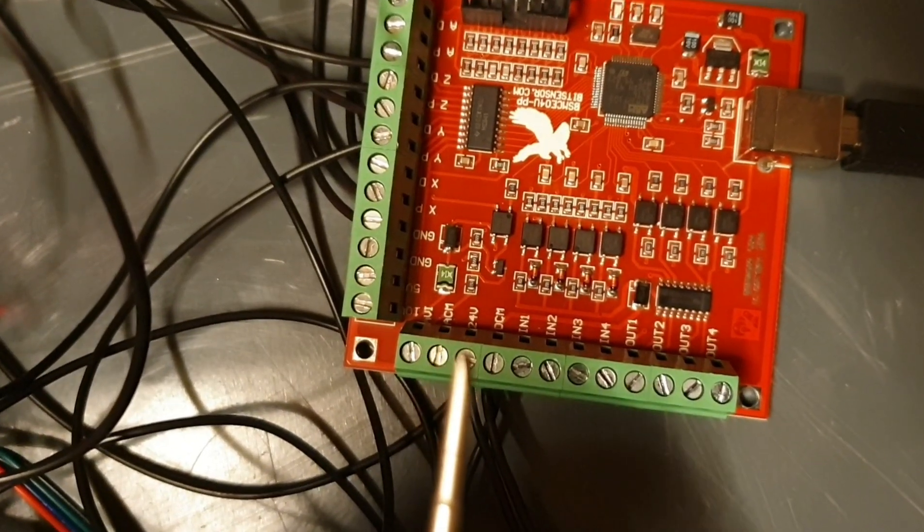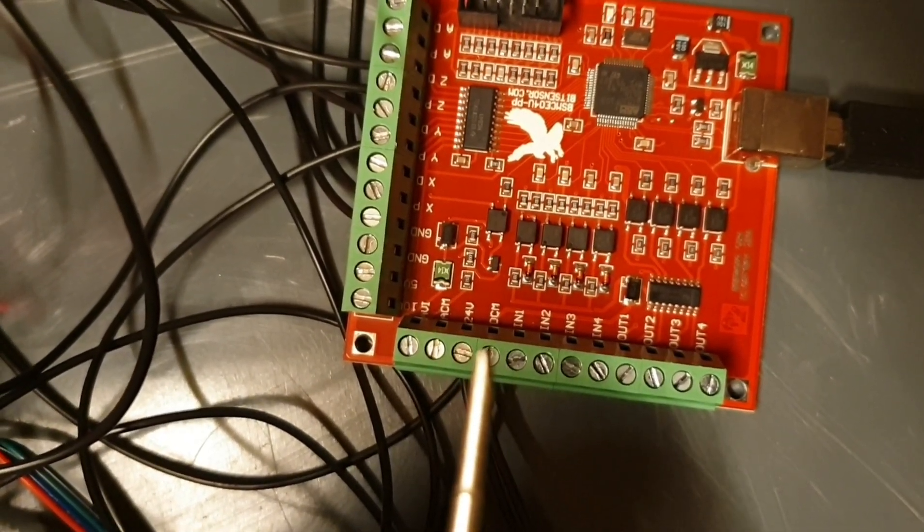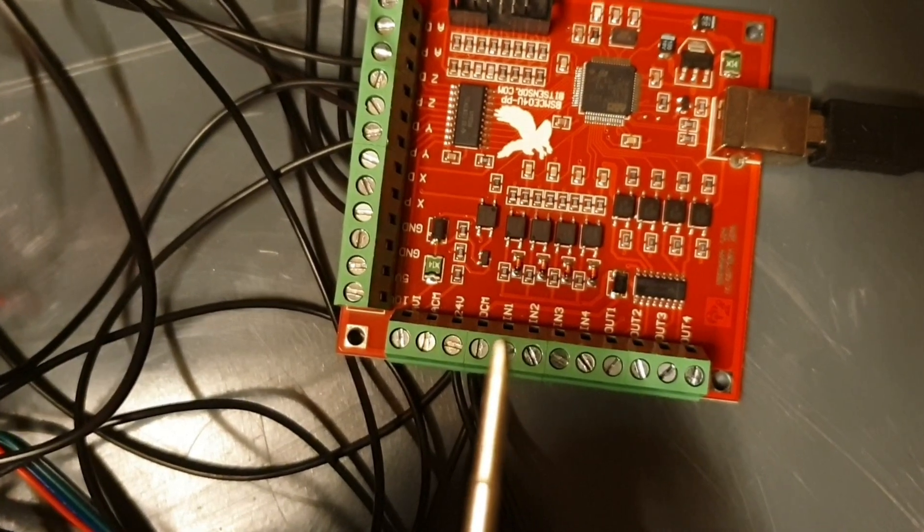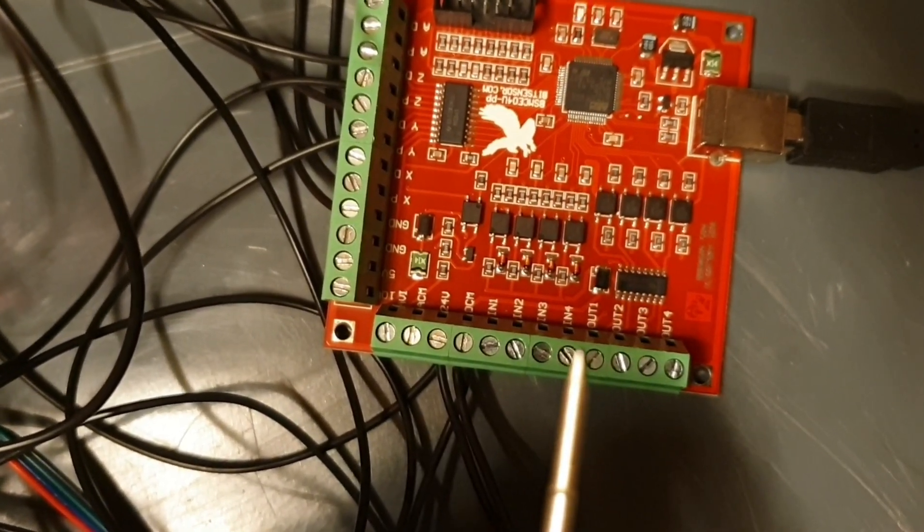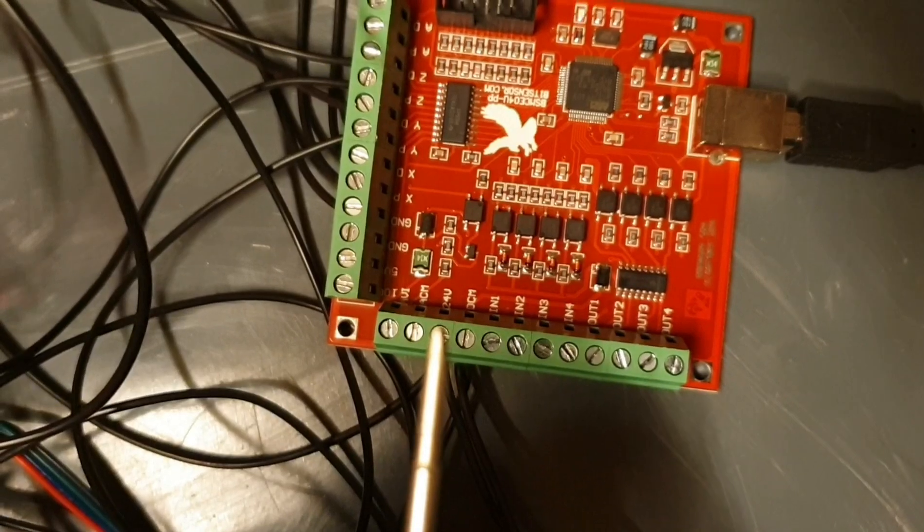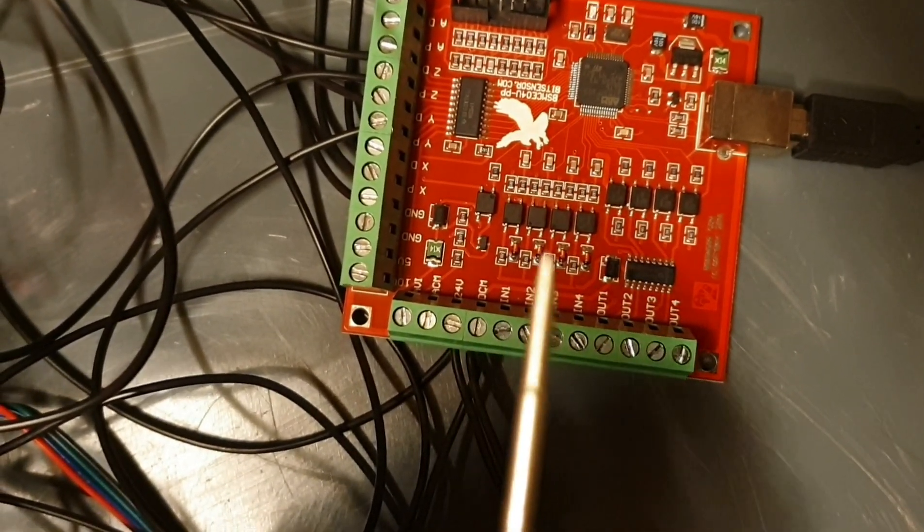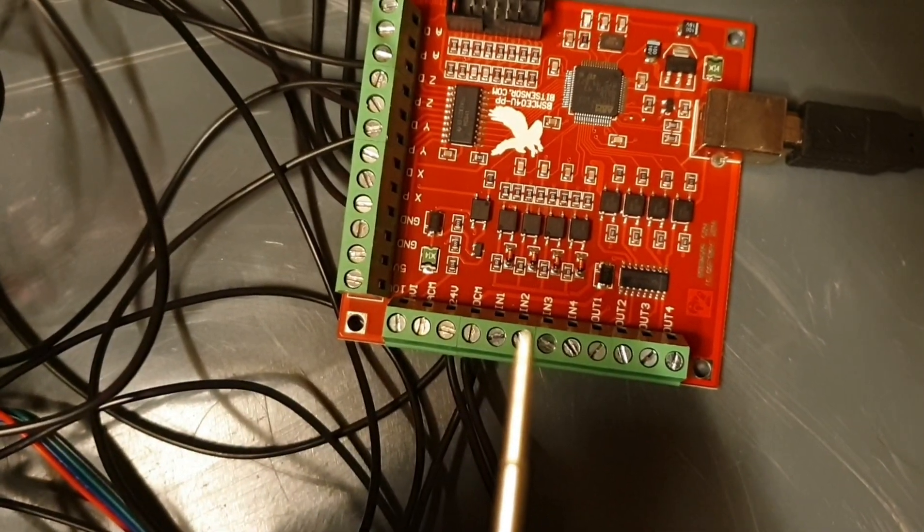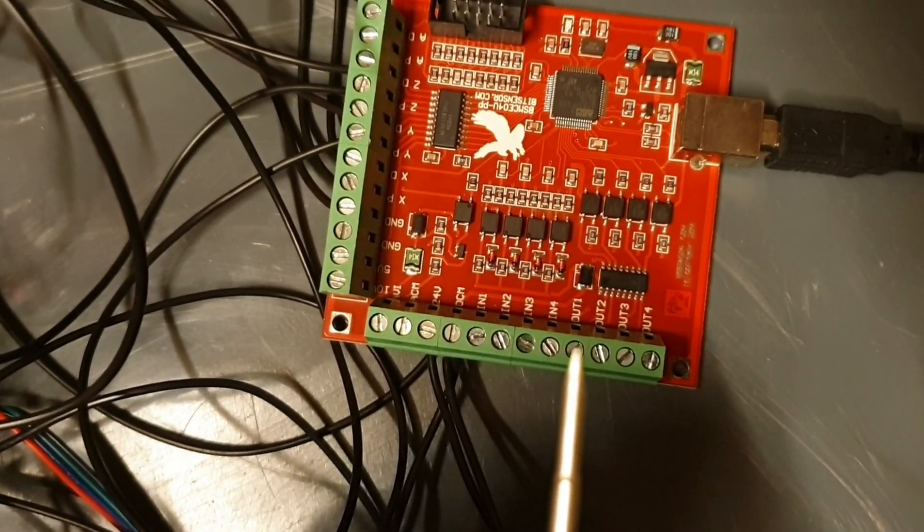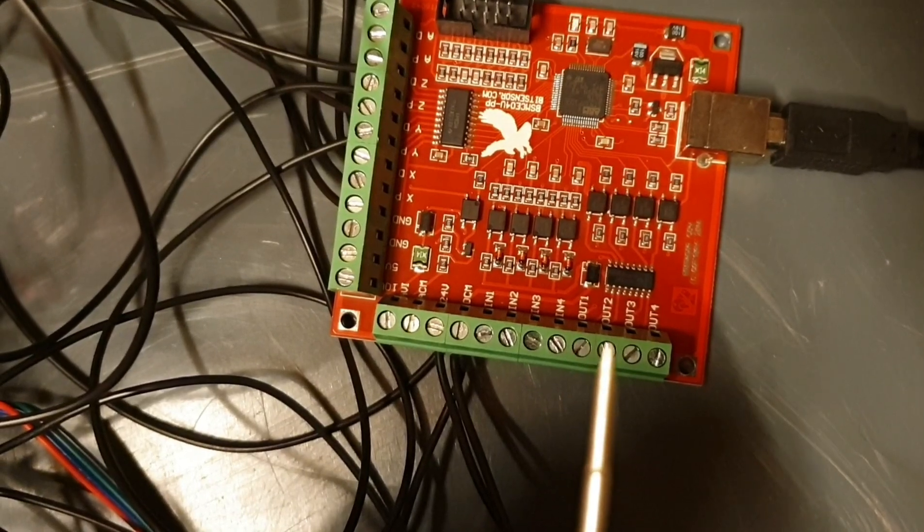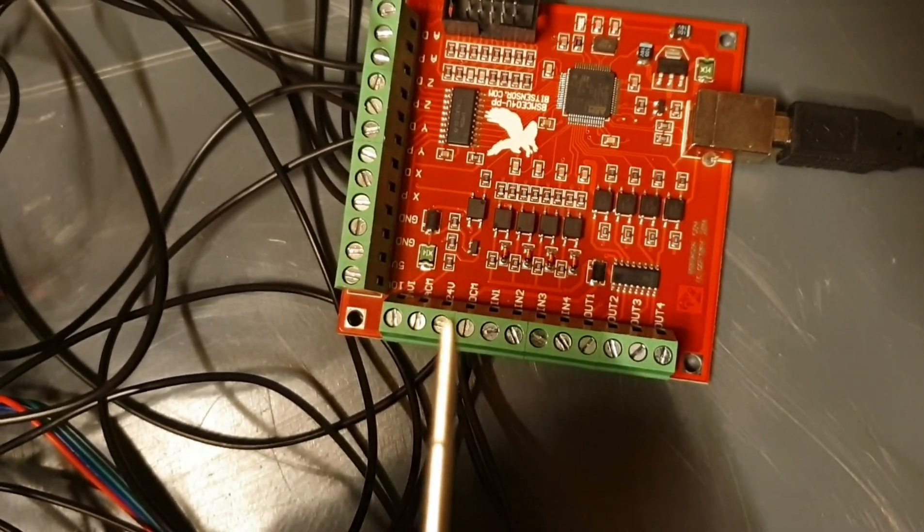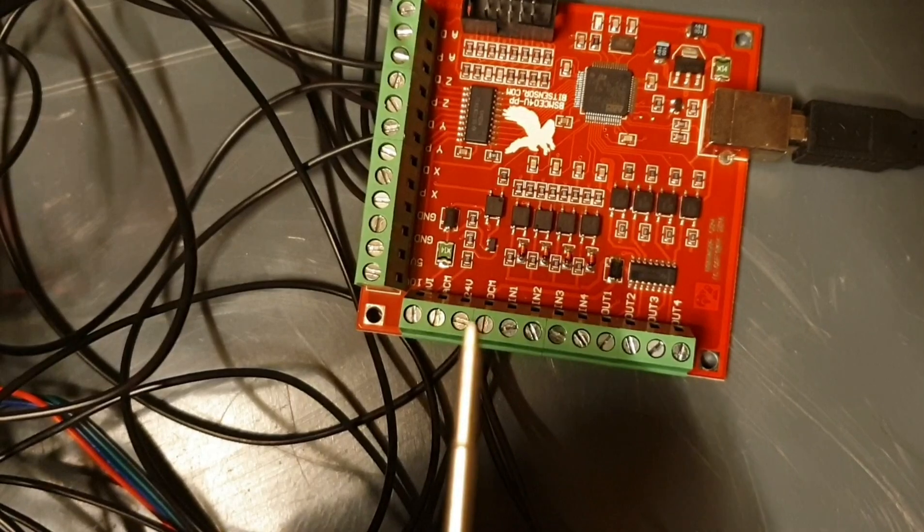24 volts on this pin and negative on this pin. And then the input channels here won't work if you don't have a connection here. Because you have to power up the other side of the electronics. Also, this output won't work without 24 volts connected here.